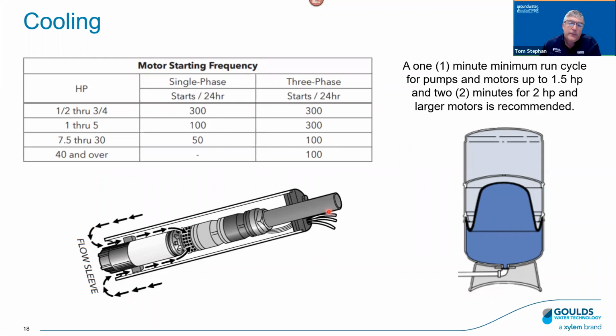Let's look here at a picture of the flow sleeve that we talked about just a minute ago. What we're seeing here is that if you do put a submersible pump in a large body, like a tank or something like that, there are two things to think about. One is the flow sleeve that redirects the water past the motor for proper cooling. And the other thing is, due to the thrust bearing, we want to tip that up 15 degrees from horizontal to put some thrust on that bearing.